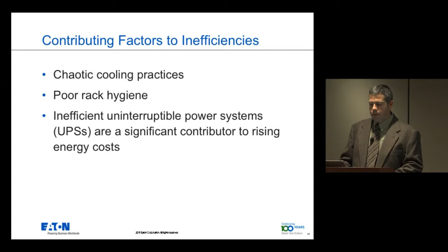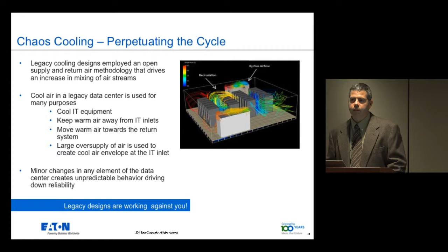But chaos cooling is, more or less, you typically will have a raised floor. You're trying to flood the room with cold air, and you're hoping, and sometimes it's a hope, that the cold air is getting to the equipment where it needs to be, and that the hot air is being sent directly back to the CRAC unit or to an exhaust system where it's not staying in the data center. I think people over time have realized that that's not always what happens. And as densities get higher, right? Different people tell you different numbers, but anywhere from 2-3 kilowatts per rack or under, this type of cooling system will work okay. Once you start getting above that, this type of cooling system breaks down pretty rapidly.